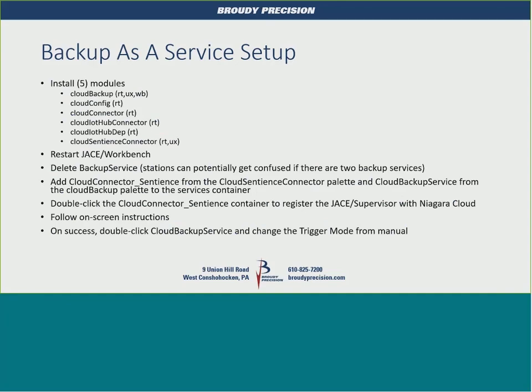And then the setup is super easy. There's 5 modules. It's actually a little bit more because of the way they break down the modules now. But it's basically all the cloud modules, all the modules that start with cloud. They get installed in the JACE or supervisor, restarted after you put them in.